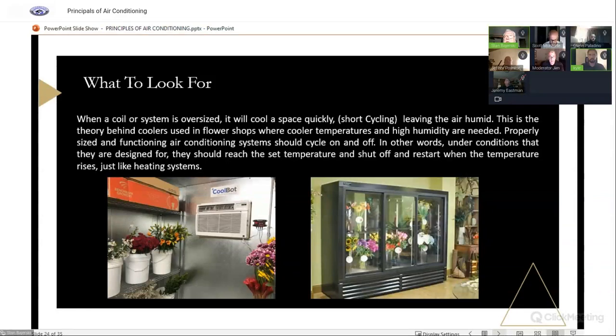We do not want to oversize the unit just in case we're going to put an addition on, because we're going to have moisture problems in that house. We're not going to be dehumidifying. And normally when you got that AC running in the middle of the summer, it's pretty humid out. So there are other reasons for short cycling, but if you hear an AC going on and off, unless it's only 70 outside, that shouldn't be.